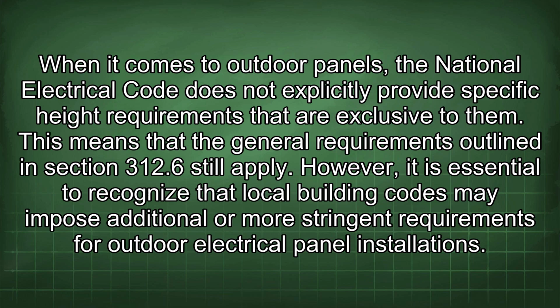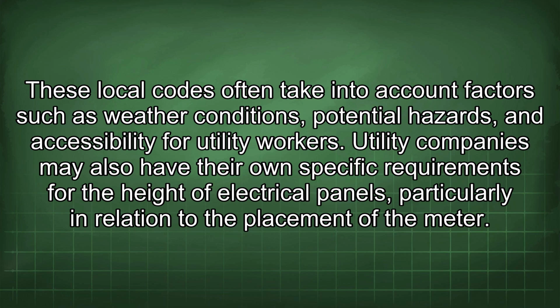When it comes to outdoor panels, the National Electrical Code does not explicitly provide specific height requirements that are exclusive to them. This means that the general requirements outlined in Section 312.6 still apply. However, it is essential to recognize that local building codes may impose additional or more stringent requirements for outdoor electrical panel installations. These local codes often take into account factors such as weather conditions, potential hazards, and accessibility for utility workers. Utility companies may also have their own specific requirements for the height of electrical panels, particularly in relation to the placement of the meter.